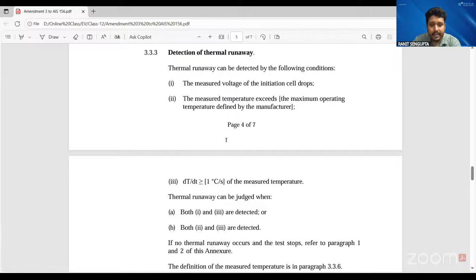The second point is the measured temperature exceeds the maximum operating temperature defined by the manufacturer. That means we have to put a temperature value as the measured temperature. As we know, above 80 or 90 degrees thermal runaway starts, so we will give nearly around 100 or 120 degree temperature. That is the second point.